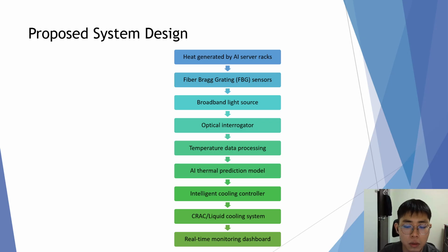So this is the proposed system design. Firstly, the heat generated by the AI server will be sensed by the fiber FBG sensor. Then the light from the broadband light source goes through to the optical interrogator. Then the interrogator goes to the temperature data processing. Then after the temperature is collected, the AI thermal prediction model will start analysis. Then we go to the intelligent cooling control. Then we have the CRAC liquid cooling system, which can help to reduce the temperature. Then after that, we will have the real-time monitoring dashboard.